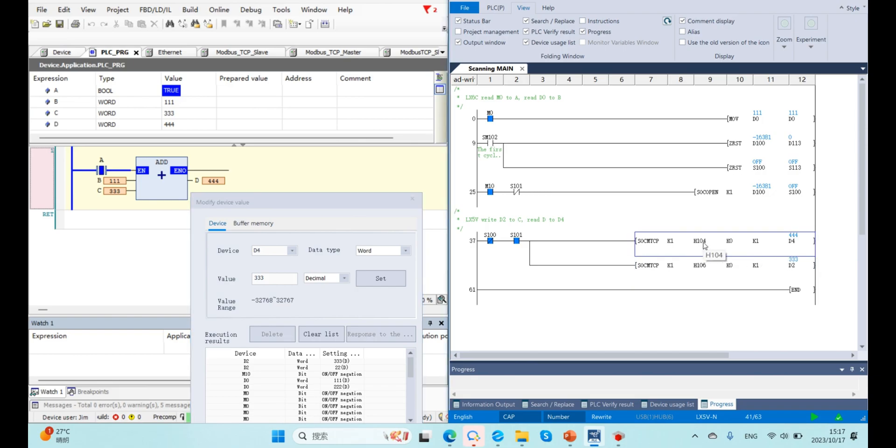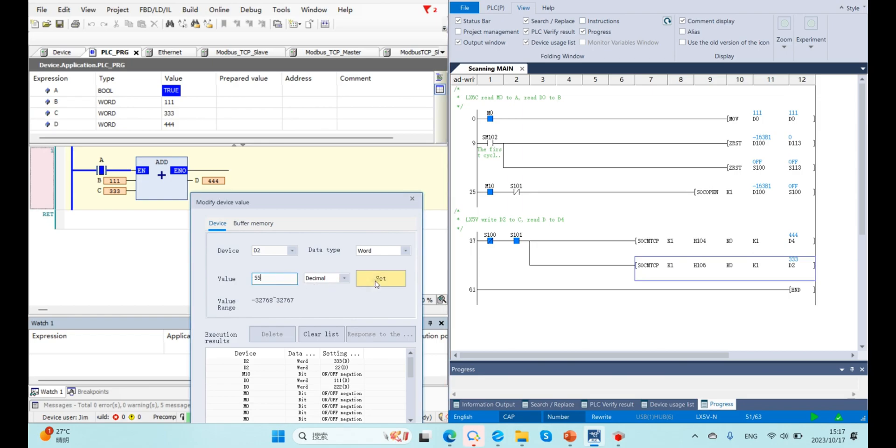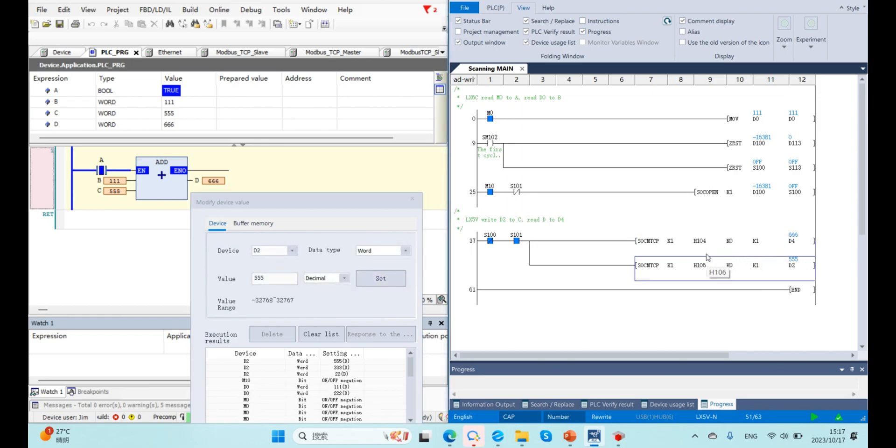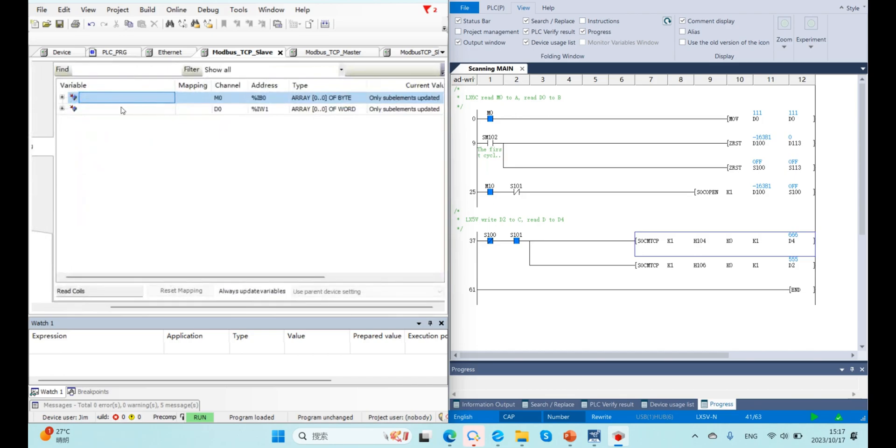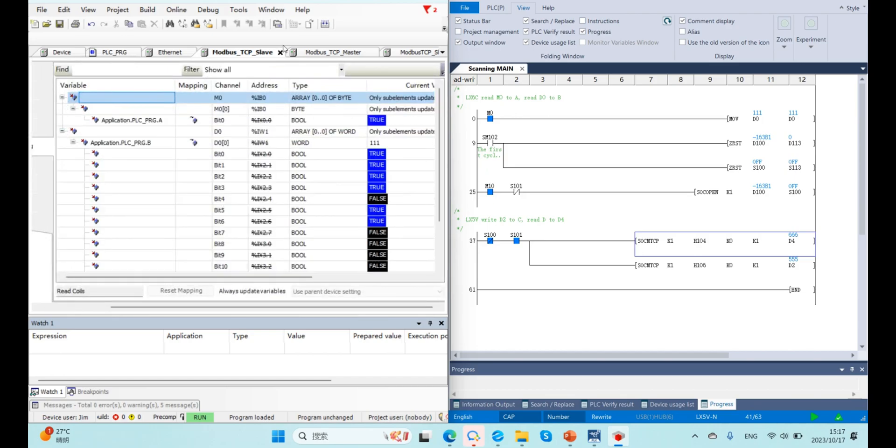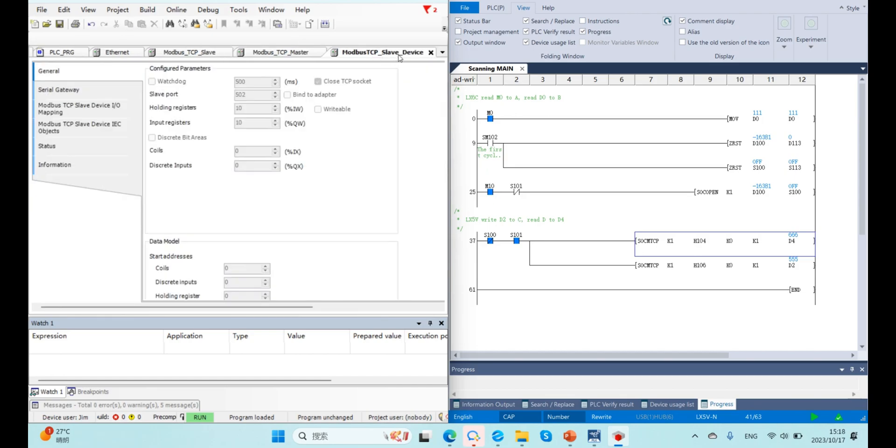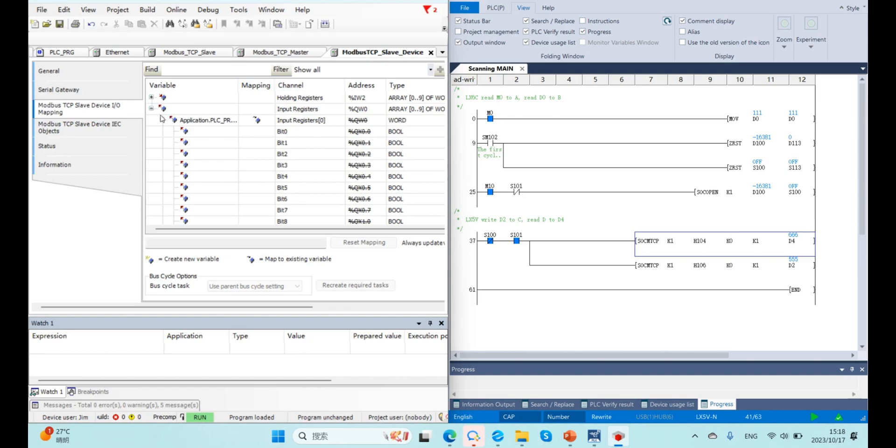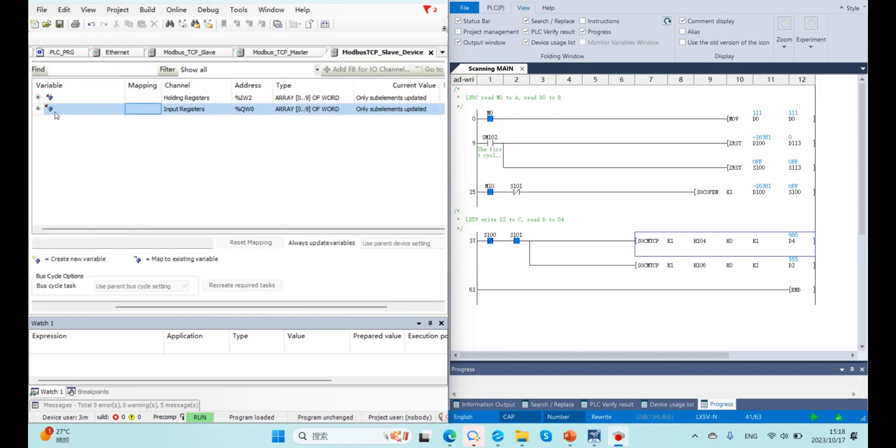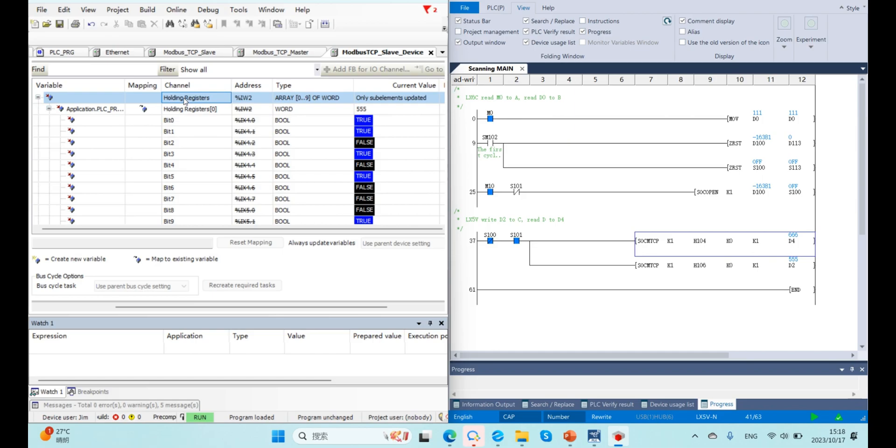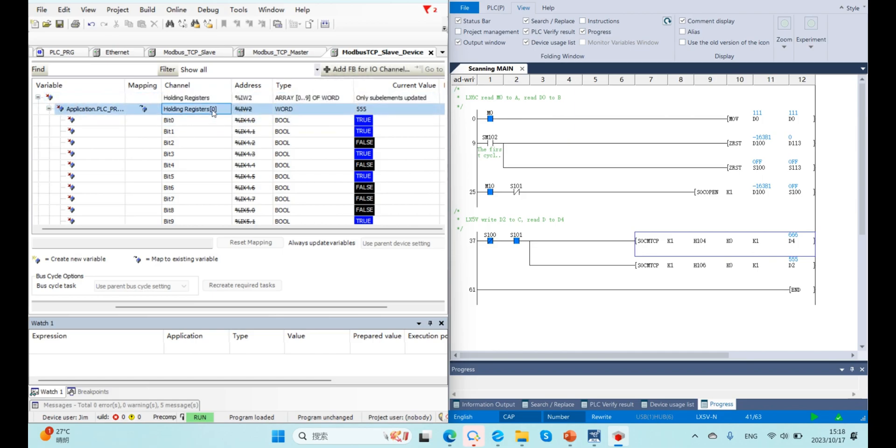And also, this Modbus code 4 means read input register. And this is register ID and register length, reading length. The Modbus code we use depends on the register type and register ID we use.